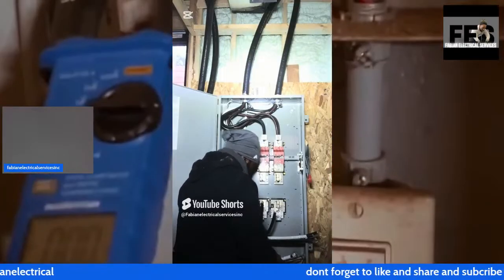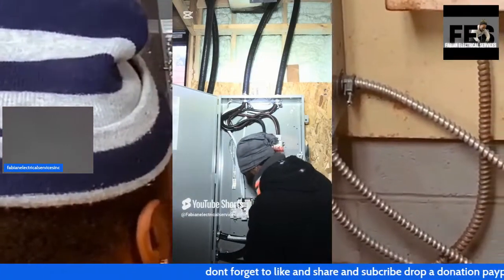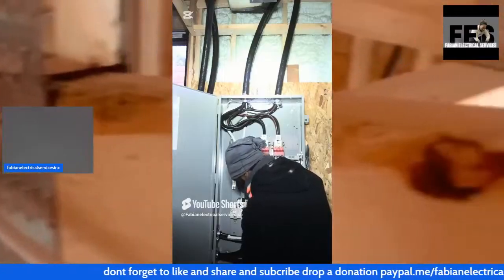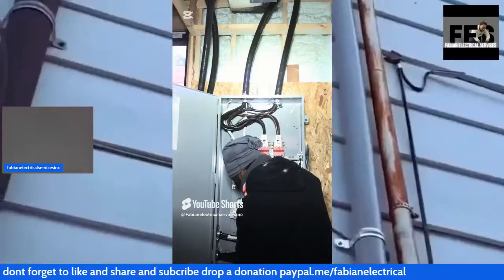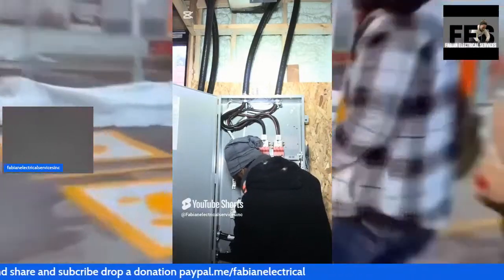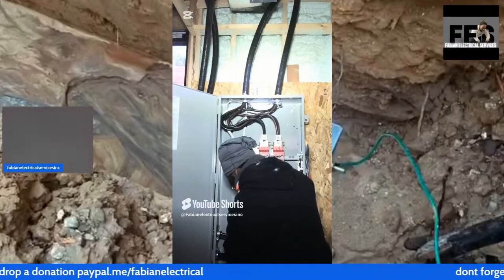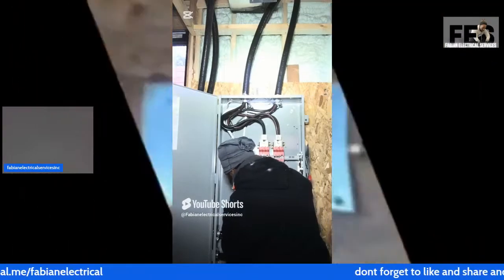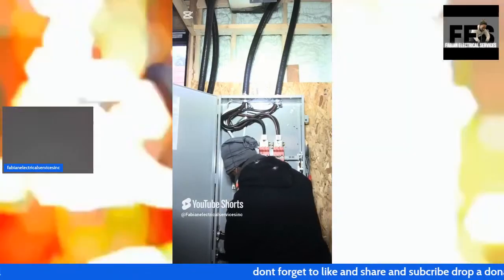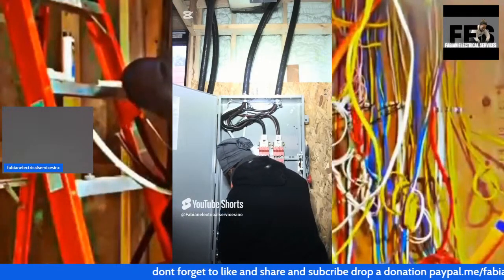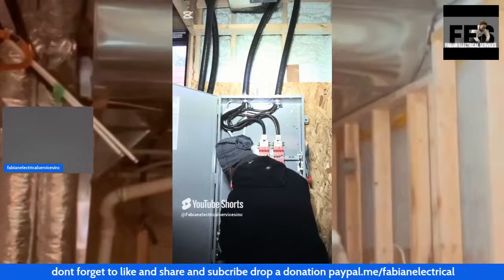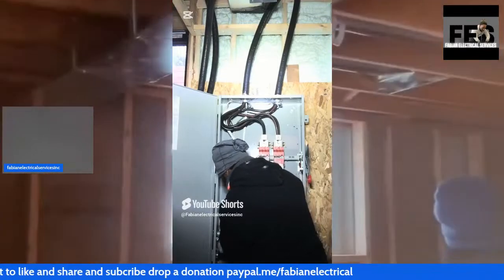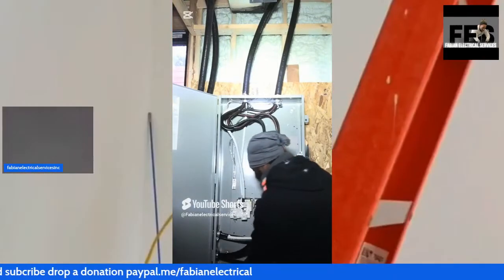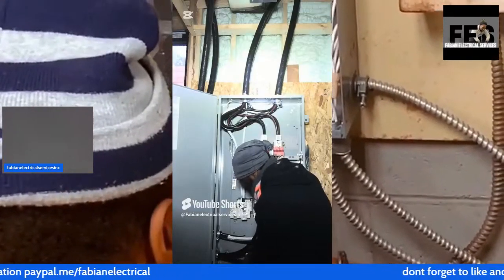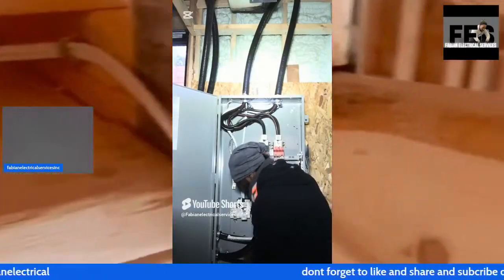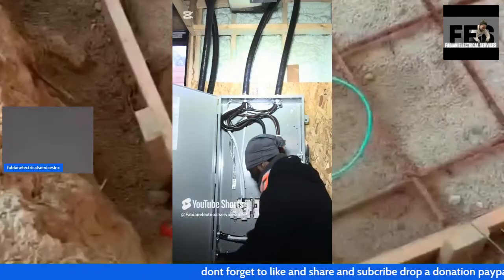A 400 amp disconnect fusible is what's here right now. The reason is because the panel is located more than a certain amount of feet from the meter base, and it's a code rule that states if the panel is located more than a certain distance from the outdoor meter base, you have to have a means of disconnect. That's what's here - a 400 amp fusible disconnect placed here because the panel is located on the other side of the home.